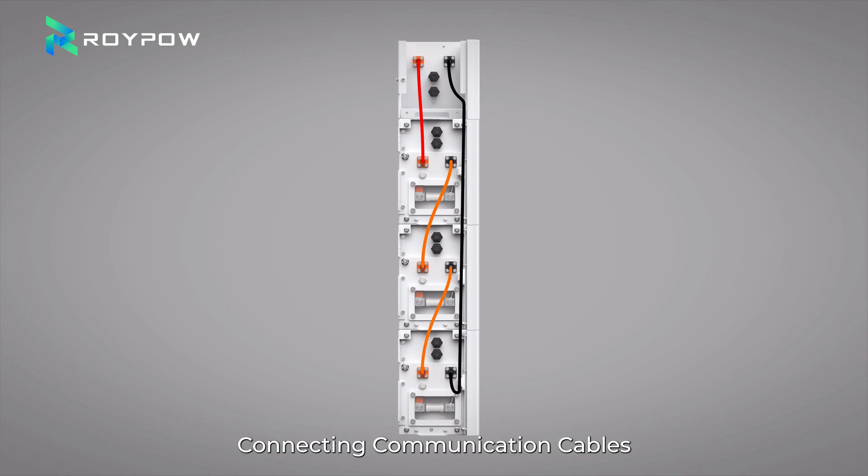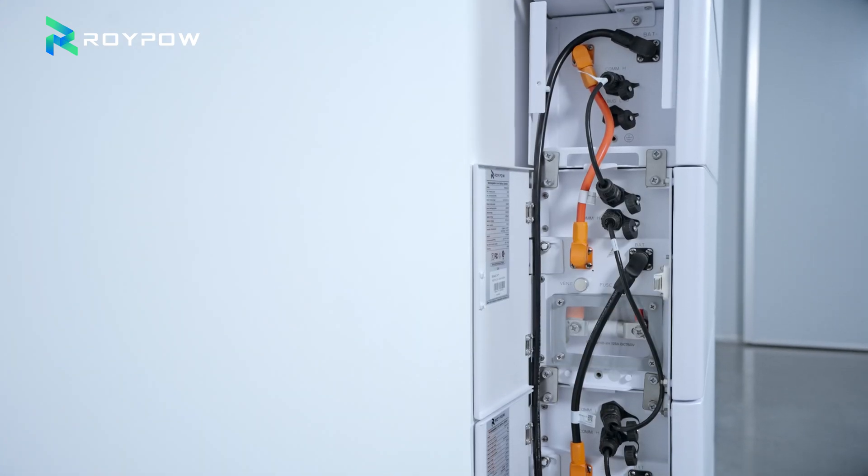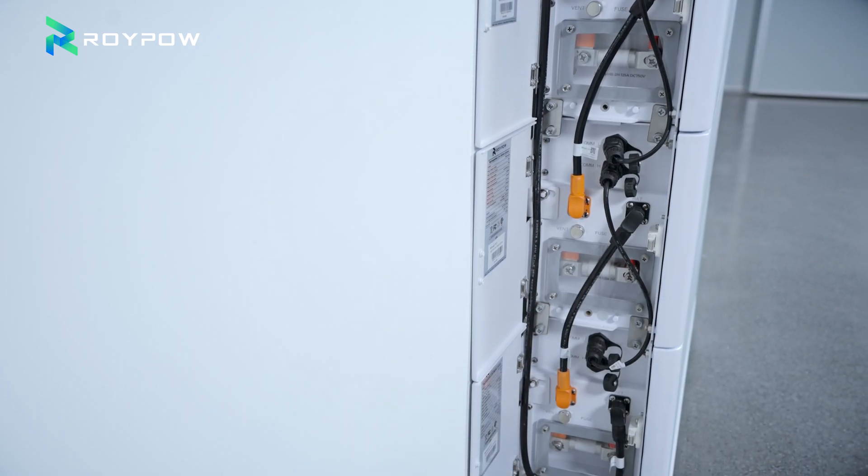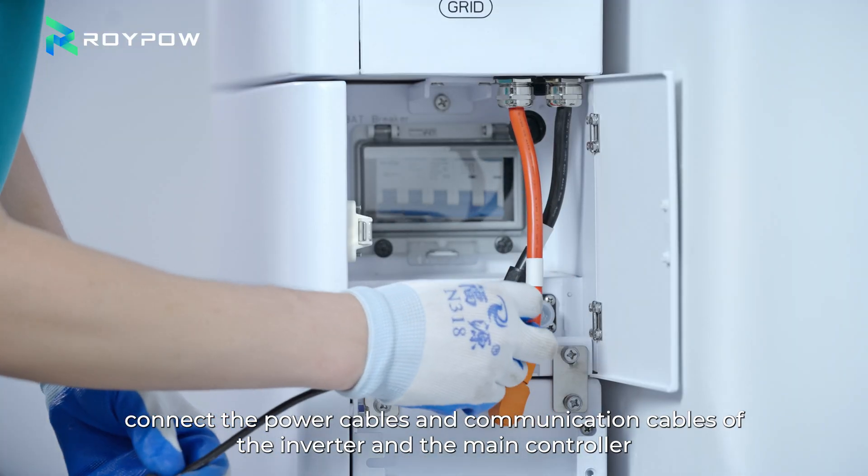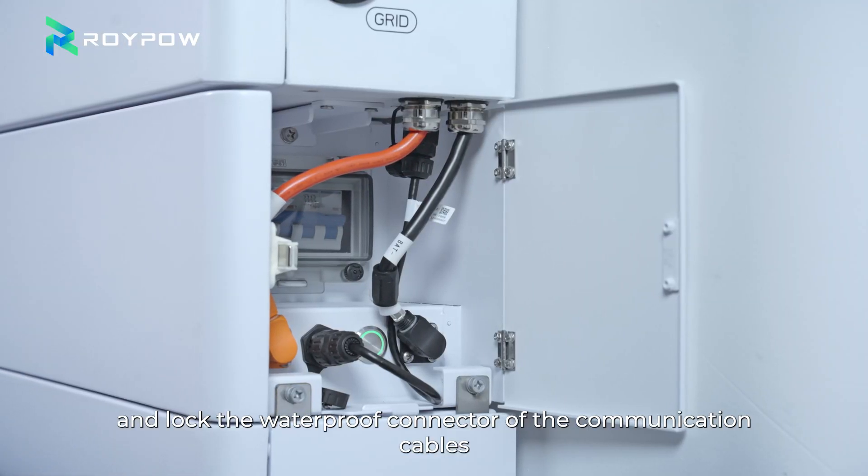Connecting communication cables. The COM-H interface of the main control box is connected to the COM-L interface of the battery. The COM-H interface of the battery is connected to the COM-L interface of the next battery, and so on. Open the right cover, connect the power cables and communication cables of the inverter and the main controller, and lock the waterproof connector of the communication cables.